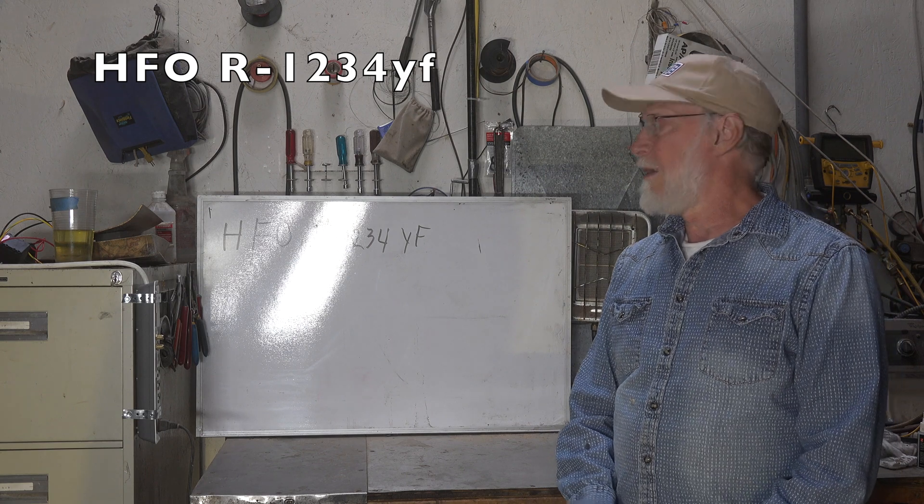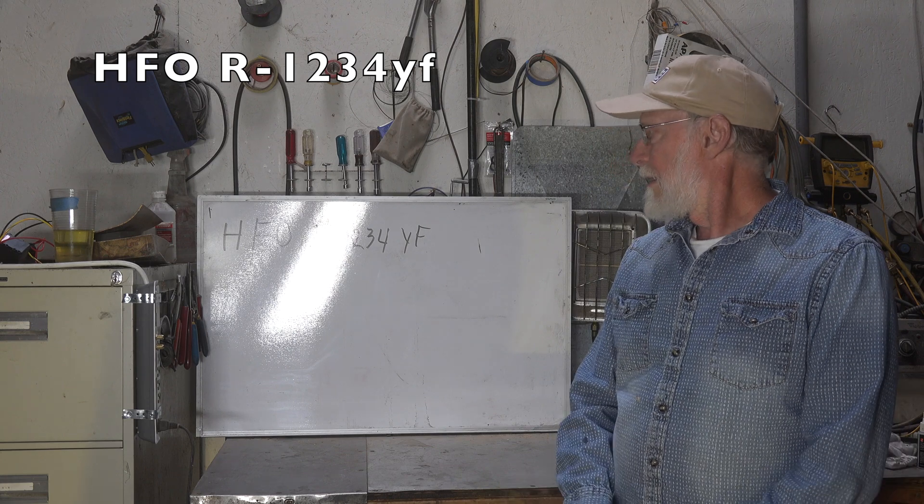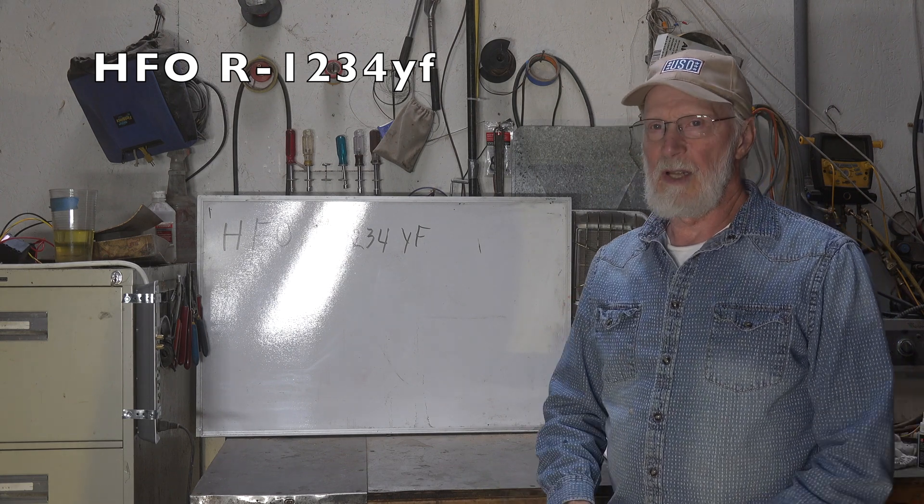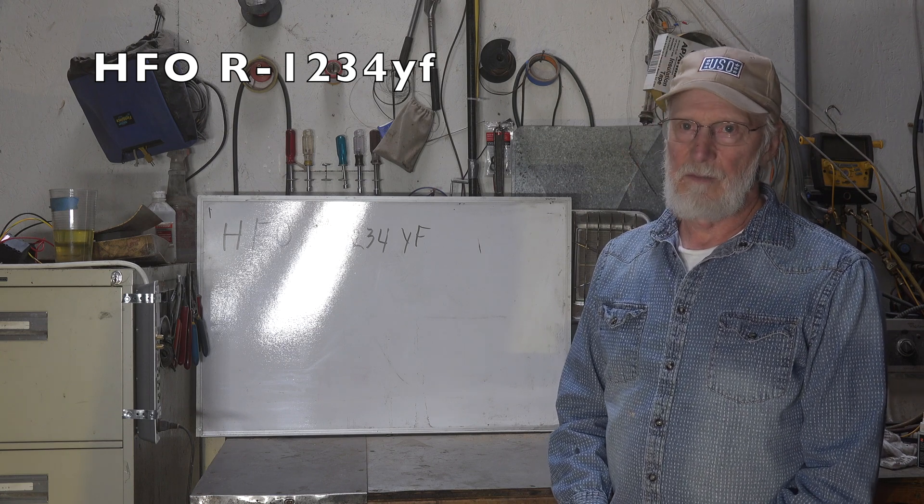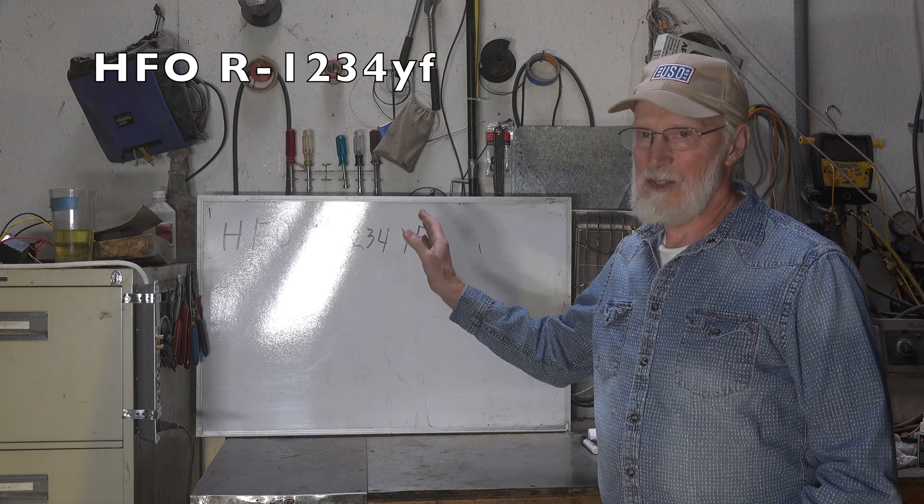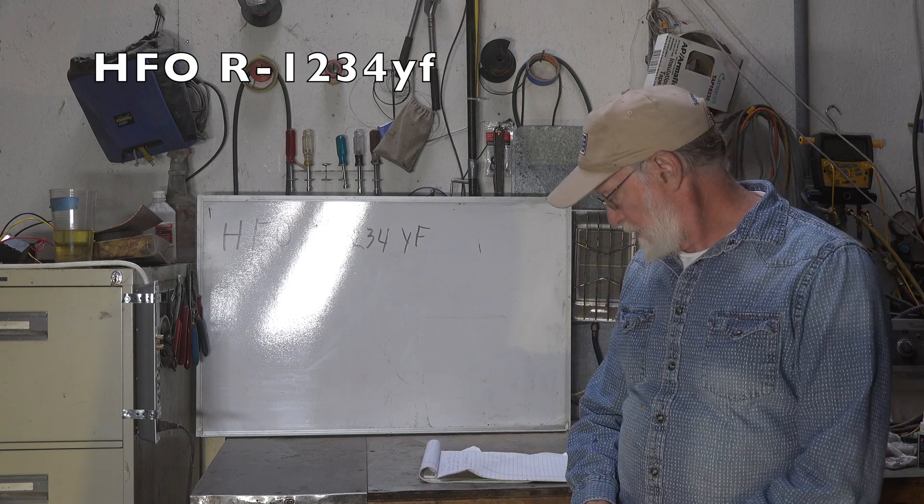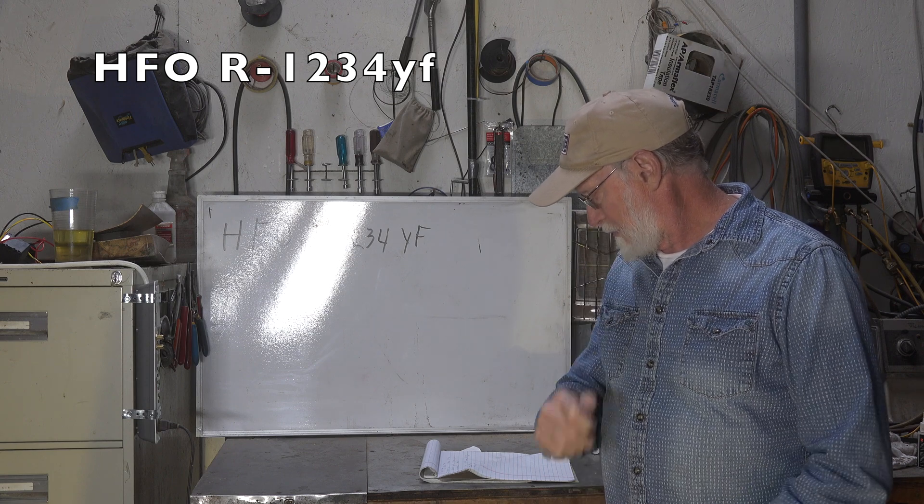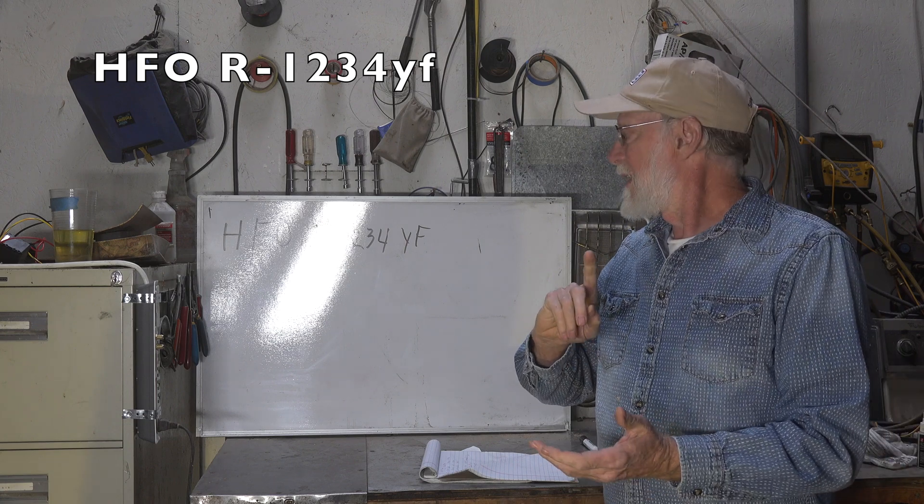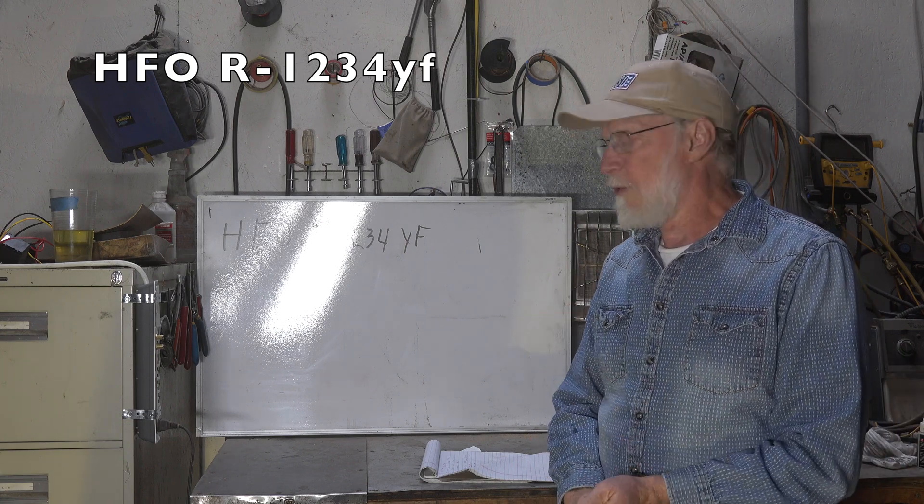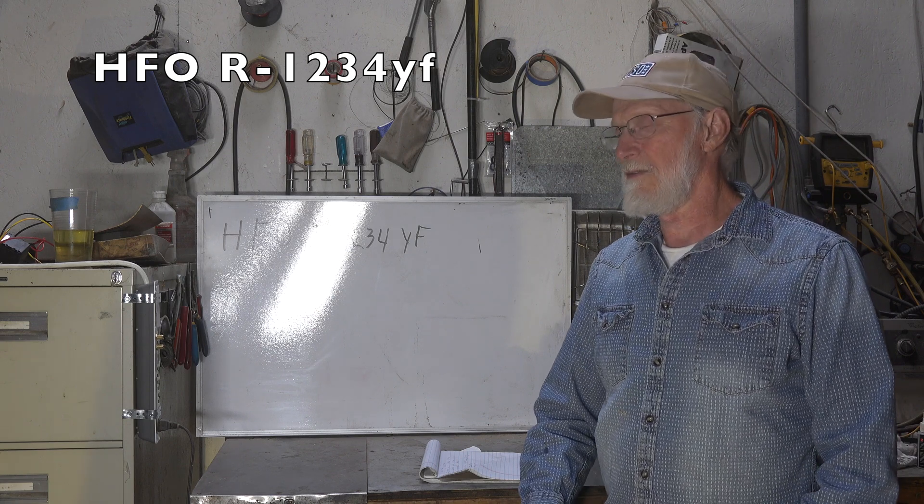R1234yf. And that has happened. We now have R-1234yf. It has a global warming potential of four. So it checks the box there. Efficiency is about the same as R134A. The biggest problem - well, not the biggest problem, but one of the problems with R-1234yf is flammability. It is flammable.